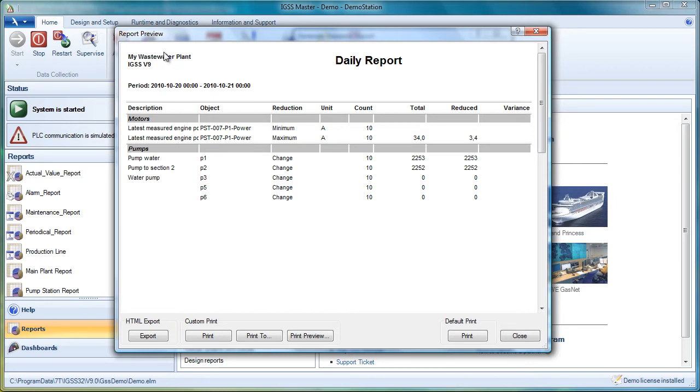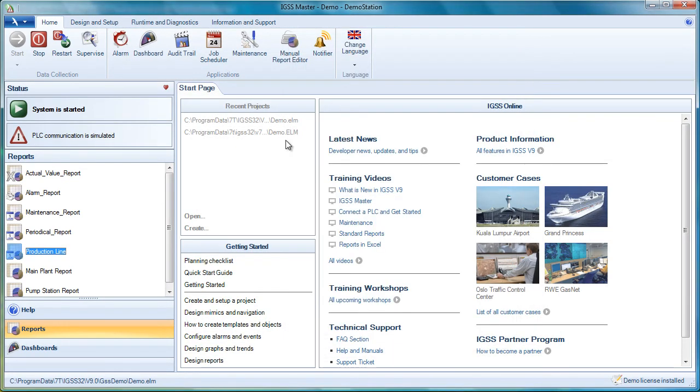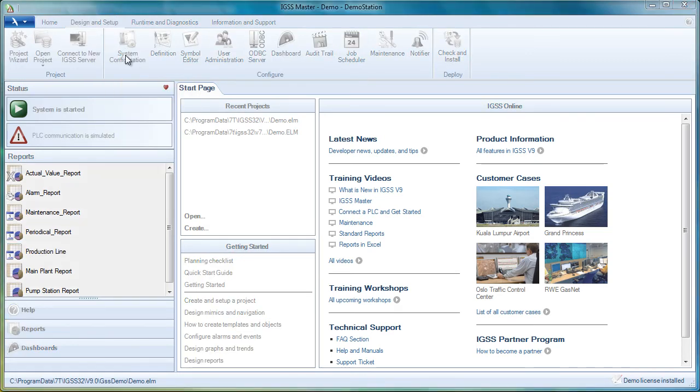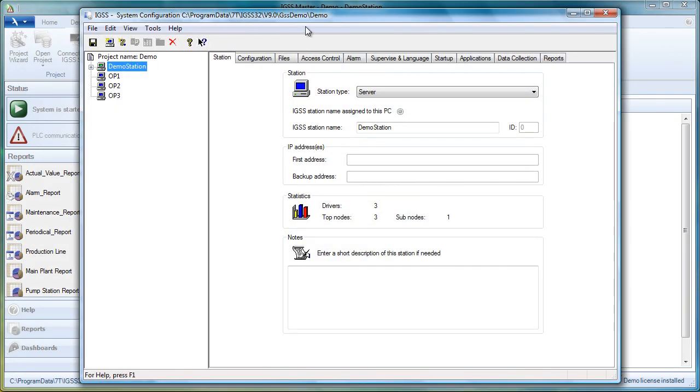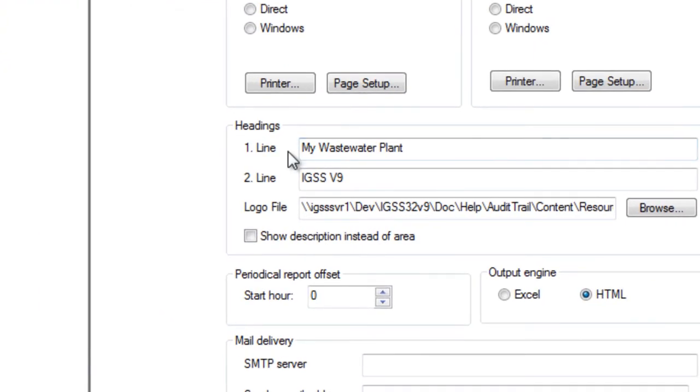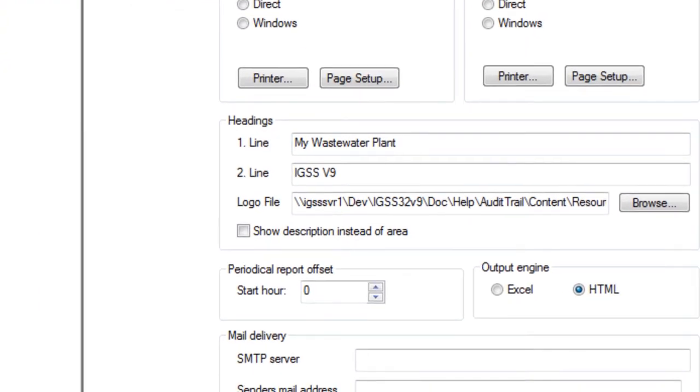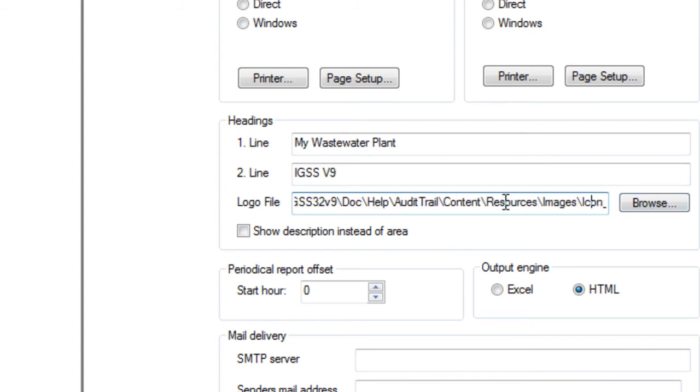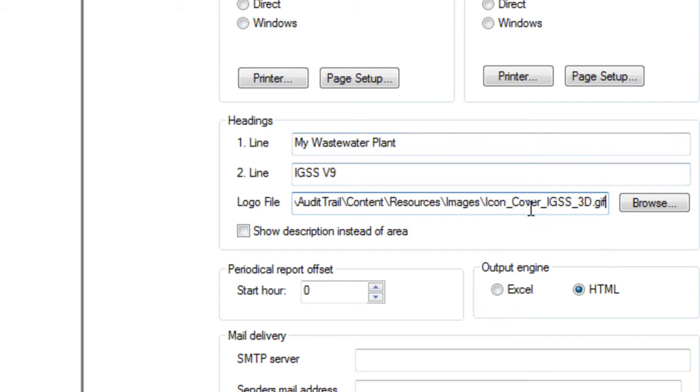And now let's take a closer look at these titles up here, because I told you that you can do them in System Configuration. So let's close this report preview, close the dialog box, and then go to Design and Setup. If we go to System Configuration, and we go to Reports, we can see that there are some setup possibilities here. My Waste Water Plant, that was the first line of the title. The second line was IGSS version 9. And then the third thing you can do is you can put in a logo. Here you can see that I have a GIF file, an icon or a logo that I'm pointing to. So the plant logo you can put up there.